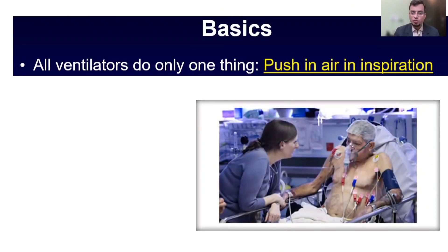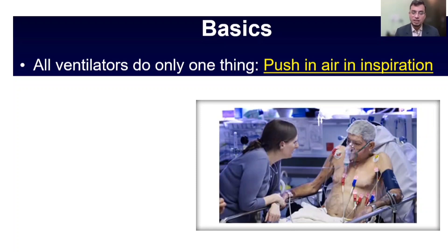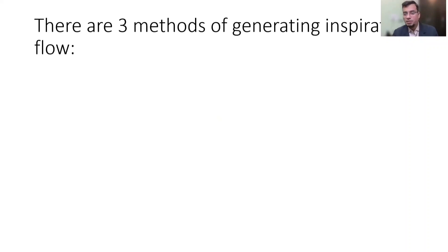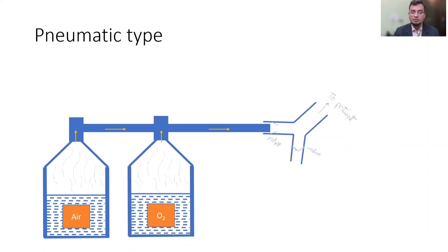Fundamentally, all ventilators do just one thing: push air into the patient's lung during inspiration. When gas moves in through the trachea to the lung it is called inspiratory flow, the demand for which is quite high in critically ill patients who do not have enough capacity to generate that flow themselves — therefore a ventilator is needed. There are three main methods of generating inspiratory flow: pneumatic, piston, and turbine.